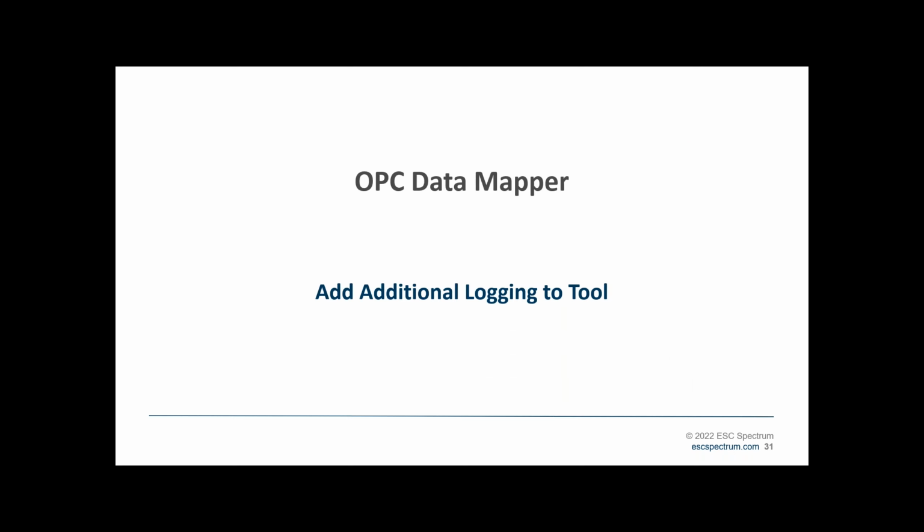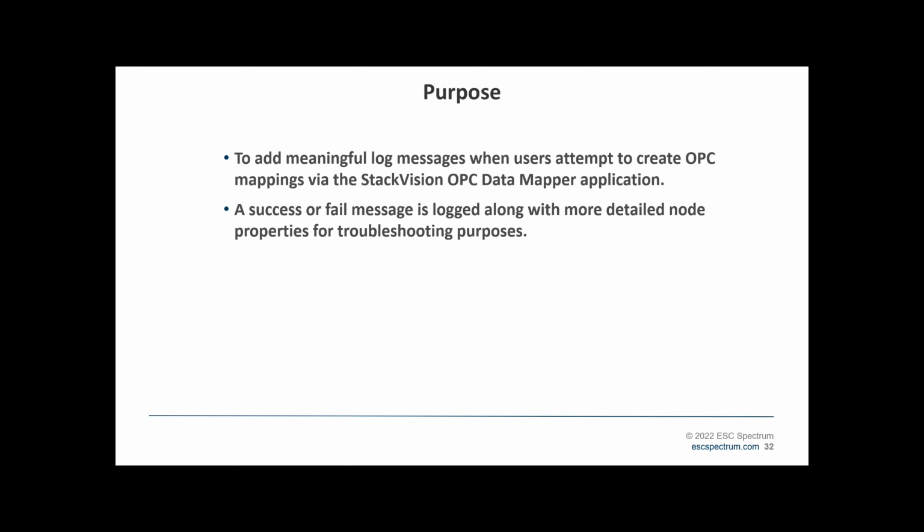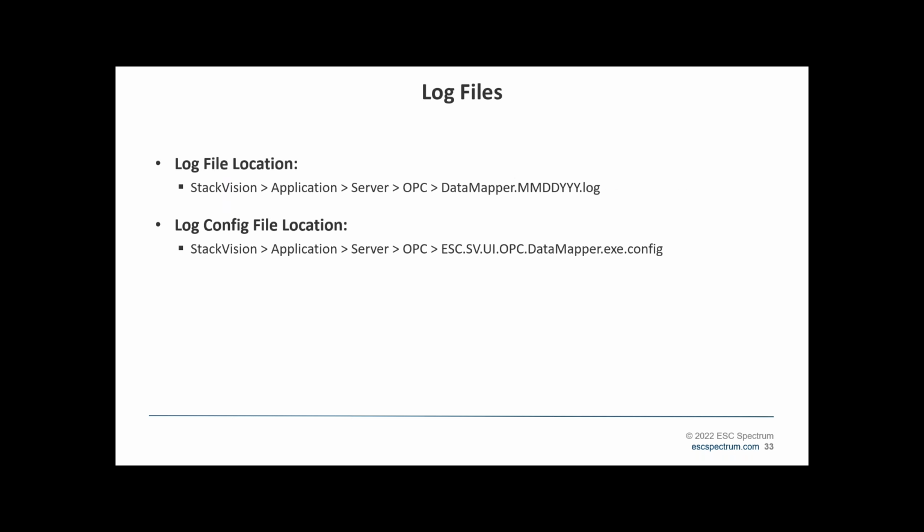OPC Data Mapper, add additional logging. The purpose of this is to add meaningful log messages when users attempt to create OPC mappings via the StackVision OPC Data Mapper application. A success or fail message is logged along with more detailed information for troubleshooting purposes. The log file and log config file are both located in StackVision, Application, Server, OPC.